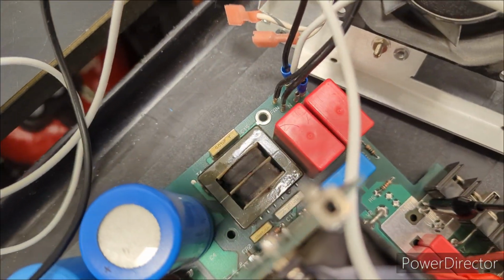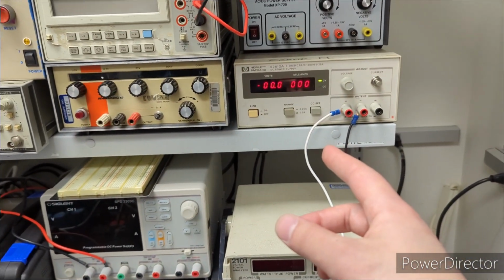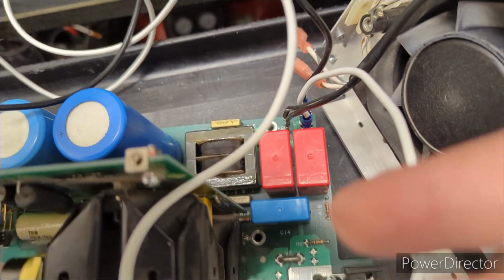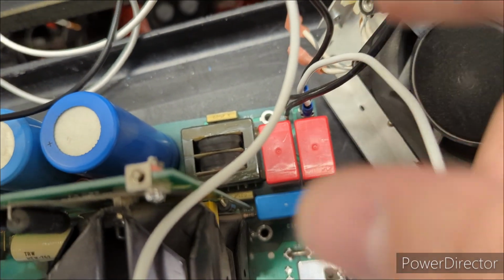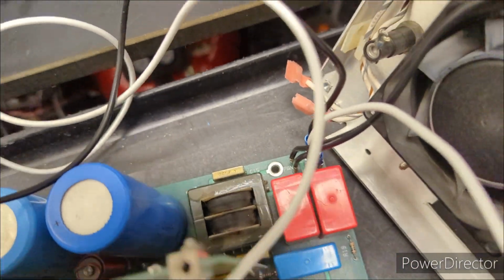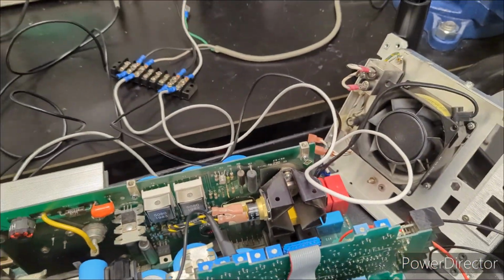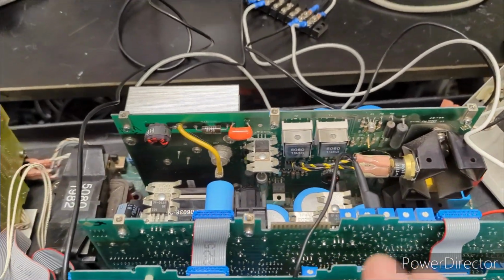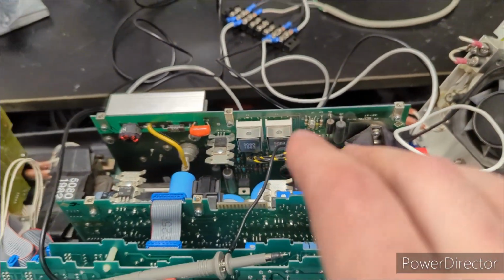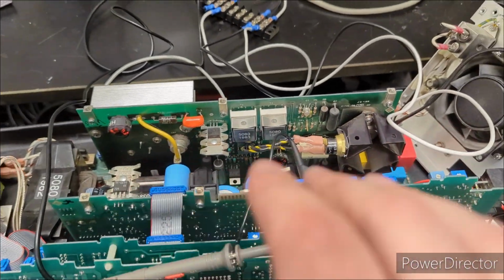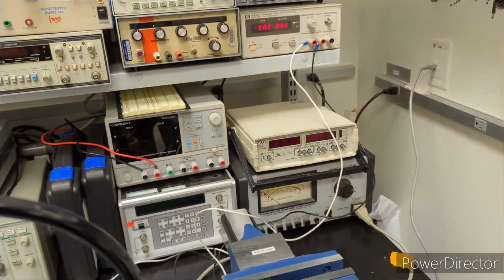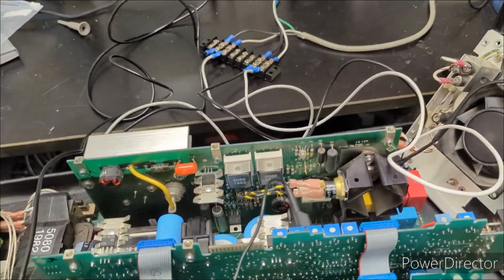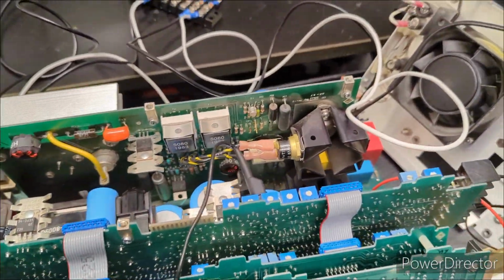They also have you set up an external power supply, which I'm using this HP E3612A. They have you connect that to the AC receptacle, and that's where the EMI filter would connect, at the line and neutral connection. So that's what I have connected there. They do that so you have a bit more control over the bus voltage for the power mesh board. Normally that's sitting at about 320 volts DC, so you can control it to a much lower voltage using an external power supply. That way, if there are any issues, you mitigate the damage that could be caused.